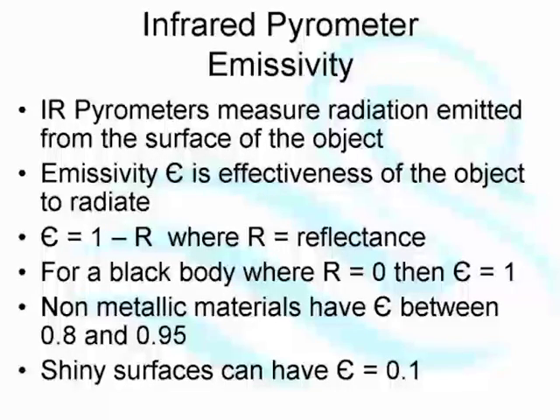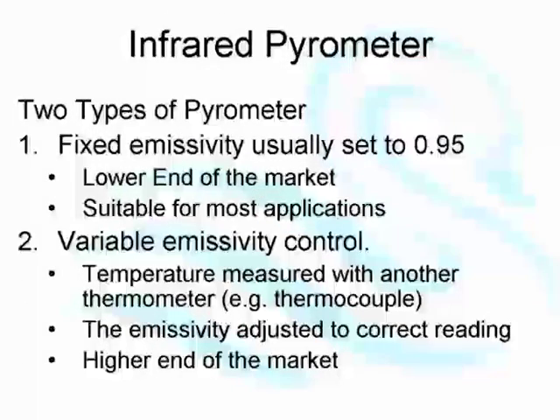Black surfaces have emissivities of around about 0.8 or 0.95. White surfaces have emissivities of around about 0.2 or 0.3. A shiny metal surface will have an emissivity as low as 0.1. If you try and use an infrared temperature sensor to measure a shiny object, you will get a ridiculous reading. It will be out by lots and lots. If the object is actually at about 80 degrees C, the infrared temperature sensor will read maybe 20 or 30. So this emissivity is a measure of how good an object is at absorbing or emitting heat.